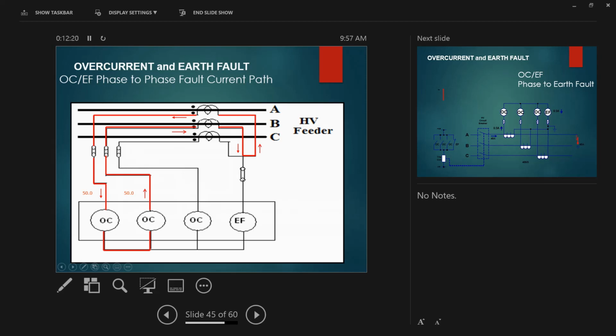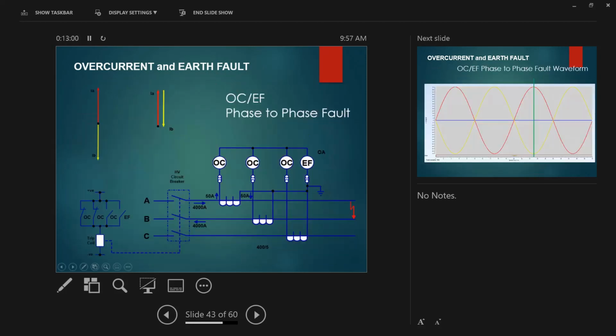So you don't disable the earth fault from the relay. No. You just change the connections on the Omicron. Not change the connection, just inject 180 degrees apart. Okay, so let's say I want to do A to B, so I'll put my red lead on A and my neutral lead on B. No, you don't need to change any connection setup. The connection is the same. It's just the angle from the software. Correct. You have to set this one here to 180 degrees.